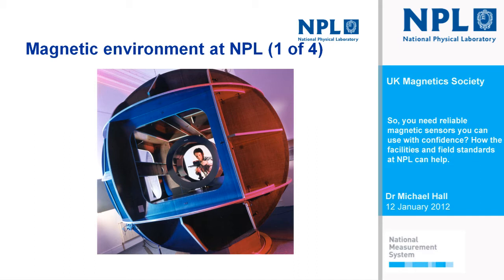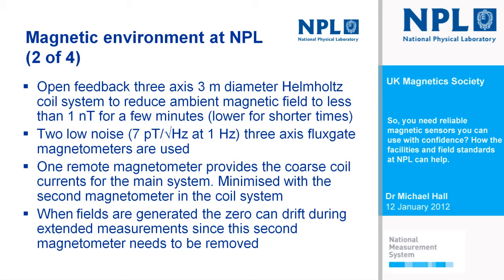So what have we currently got? Well, the system that I've just shown in the previous slide, that's an open feedback 3-axis 3 meter diameter Helmholtz coil system. And what I mean by open feedback is the magnetometer, the little black box that was being positioned in the centre of that facility, is used along with a second identical 3-axis fluxgate magnetometer, which is remote, 70 meters away, to reduce the ambient field down to less than a nanotesla. And then we have to apply fields, so that fluxgate in the lab is removed.